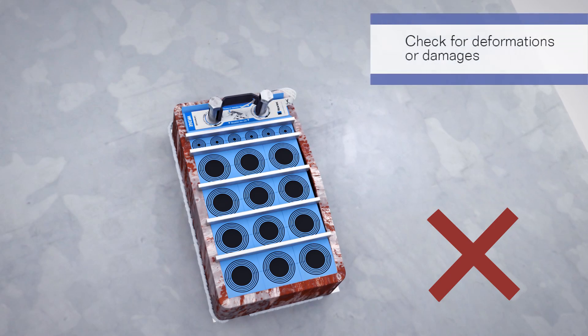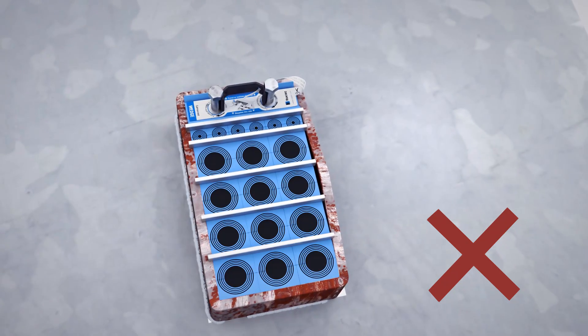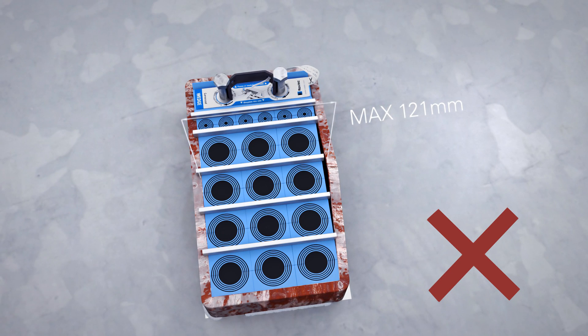Check the seal for deformation or for mechanical damage, such as excessive corrosion or incomplete welding. The internal width should not exceed 121 millimeters.